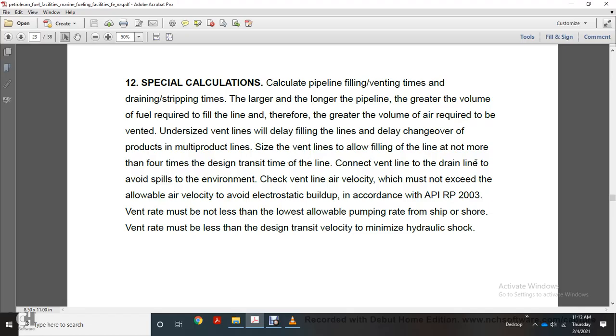Move the vent to the drain line to avoid spills to the environment. Check the vent line air velocity; you must not exceed the allowable air velocity, to avoid electrostatic buildup. In accordance with API Recommended Practice 2003, the vent rate must not be less than the lowest allowable pumping rate from ship or shore. The vent rate must be less than the design transit velocity to minimize hydraulic shock.